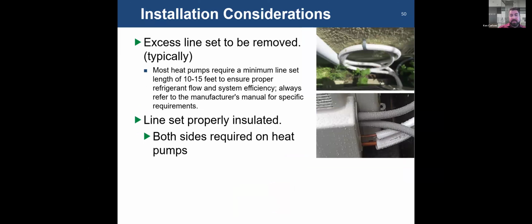Make sure to remove excess line set. There are some minimum requirements on these units as far as the minimum amount of line set, not just the maximum. Remove anything that's extra that you don't need. Just for cleanliness, make sure you're not trapping anything, trapping oil or anything such as that. Again, I mentioned your line sets being insulated properly, end to end. If you have to make connections, put tape around them, seal them tight, or glue, so that water can't infiltrate inside the insulation as well.